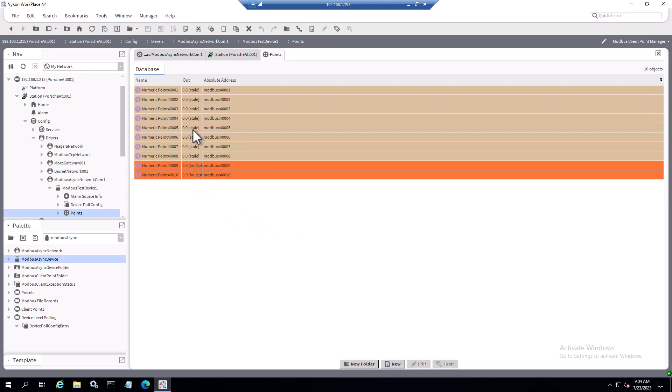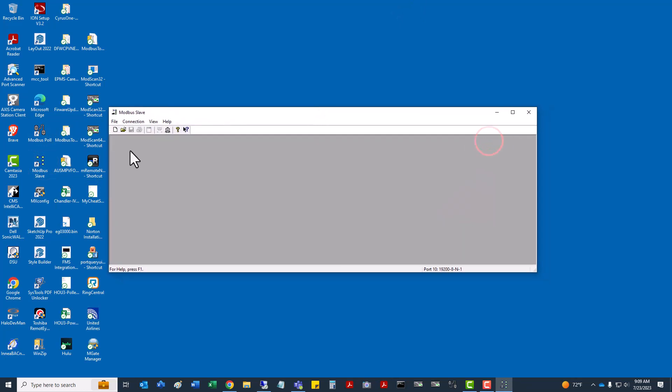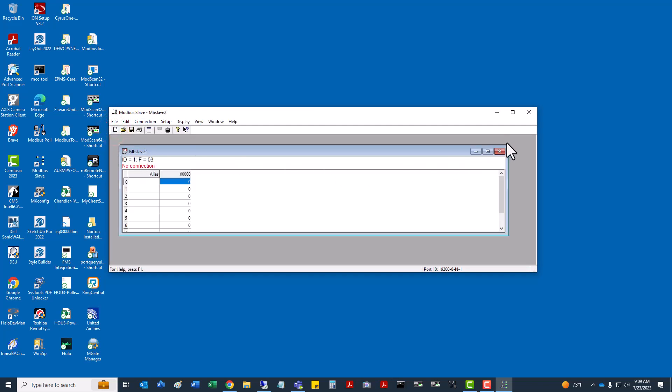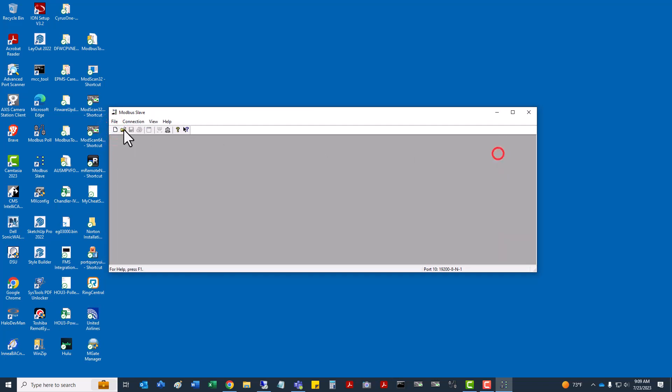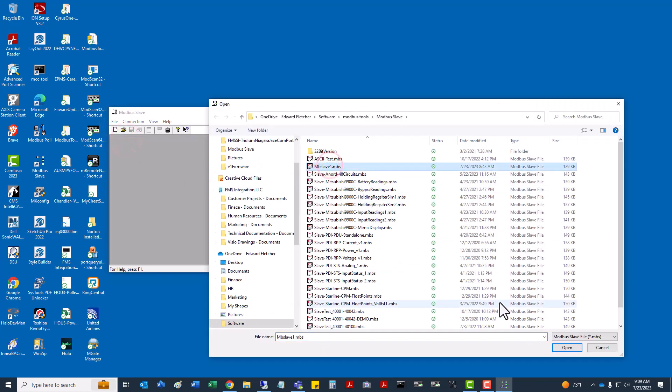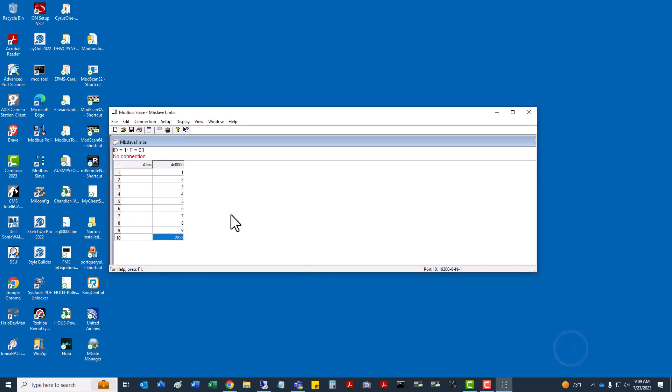I'm going to put this down in place. Then we can see everything's going to start airing out because I don't have that Modbus simulator running. On here I'm just going to minimize, go over to my Modbus Slave. I have this serial cable hooked up to the end of the RS485 line connecting to COM1. I'm going to do open file, open this MB slave. So here I have it configured for function 3, which is our 40000 set for the holding registers, ID set to 1 which matches our slave device, and then I have 400001 to 400010. This I set to auto increment.